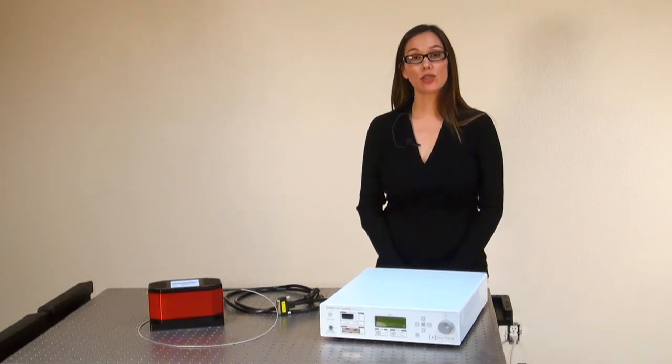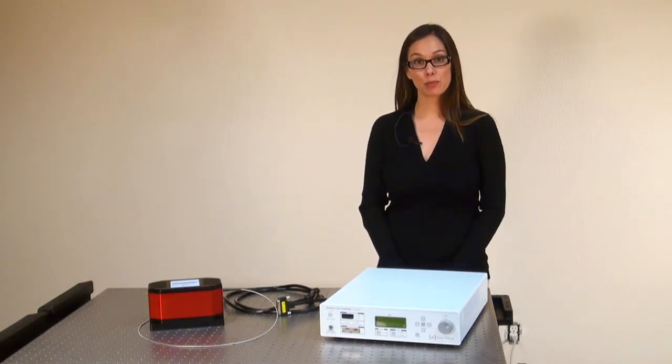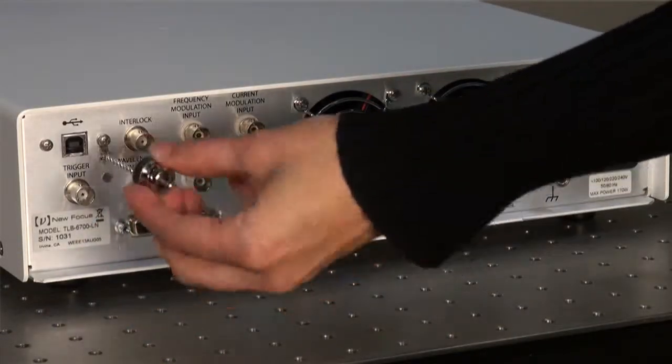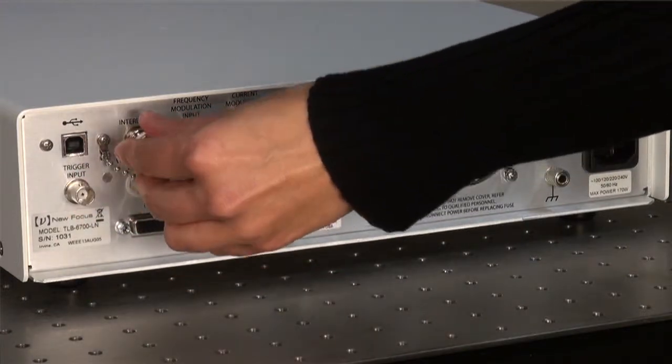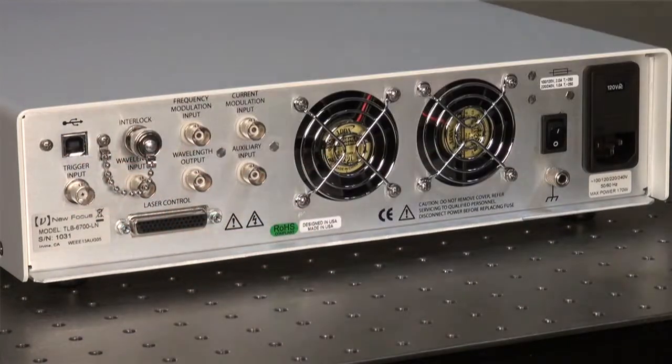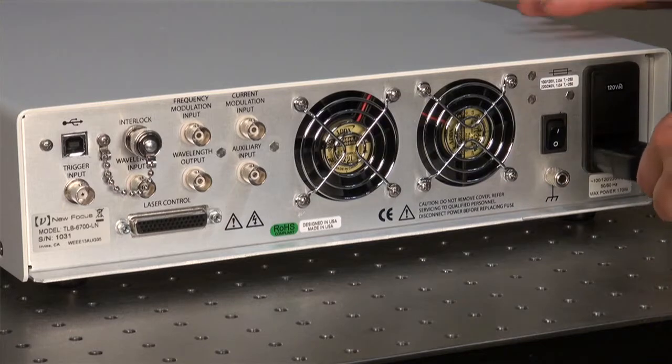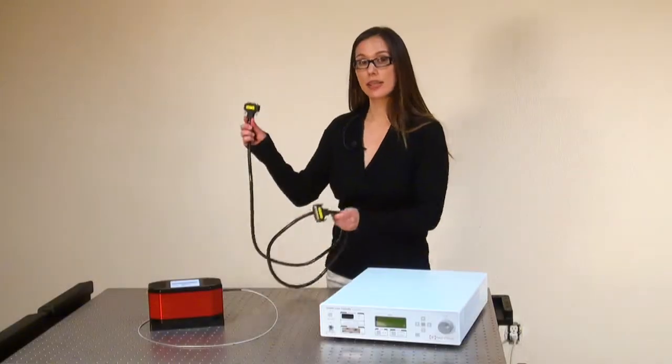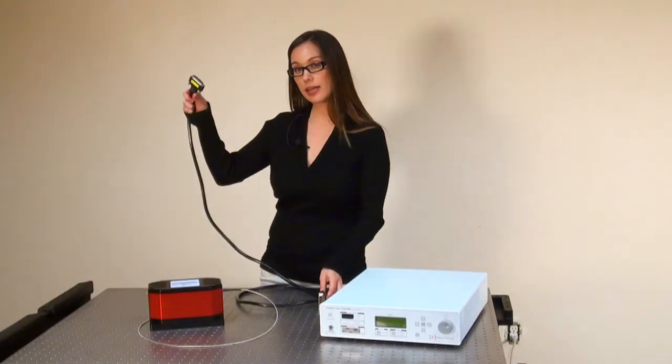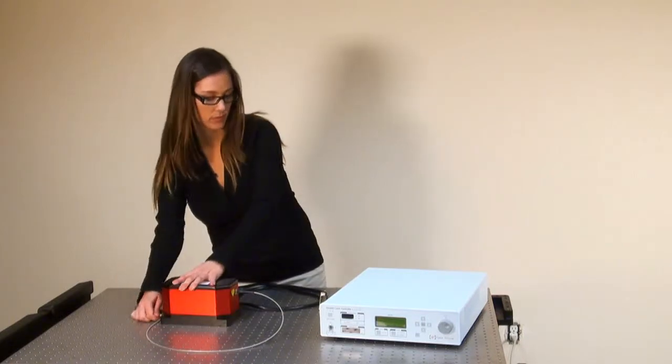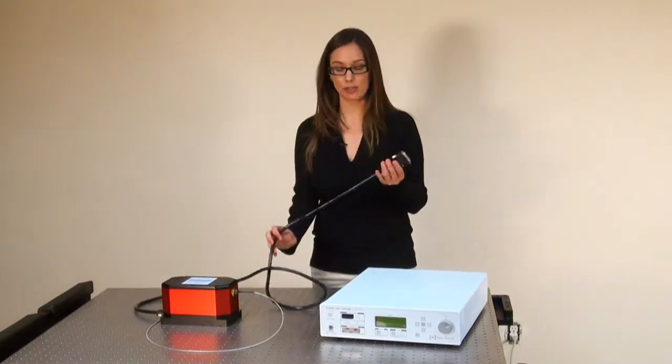To turn your laser on, ensure you have the proper fuses in place and that the interlock terminal is also in place. First, plug in the power cord. Second, take the laser cable and plug one end into the laser head and the other end into the back of the laser controller.